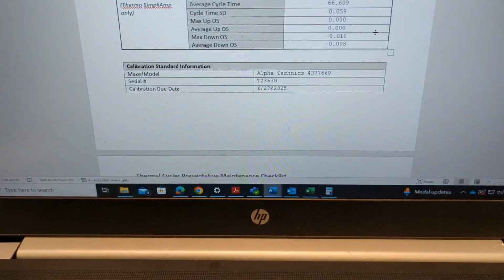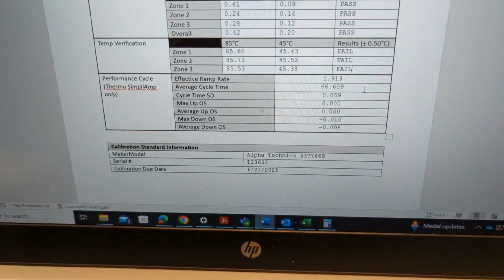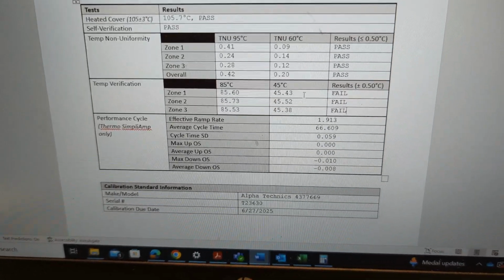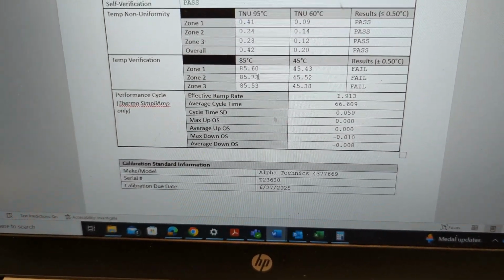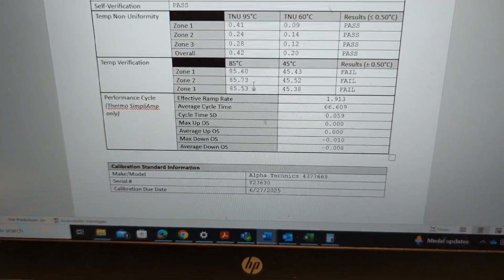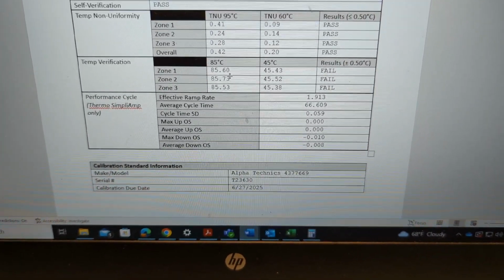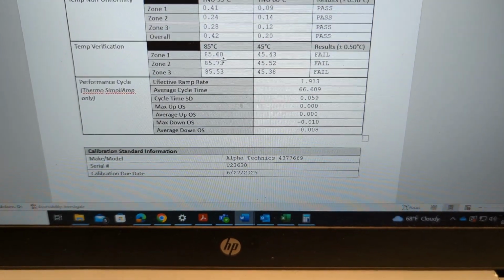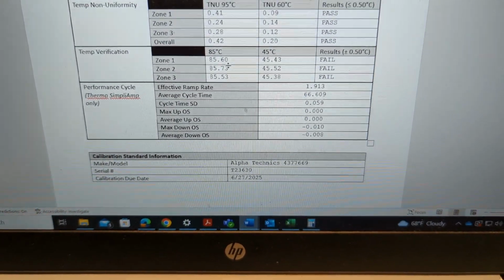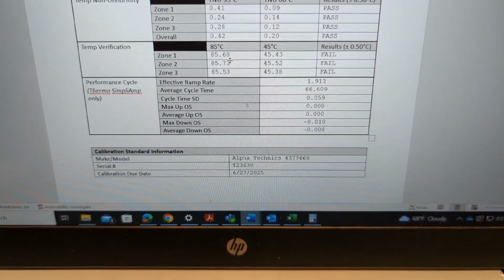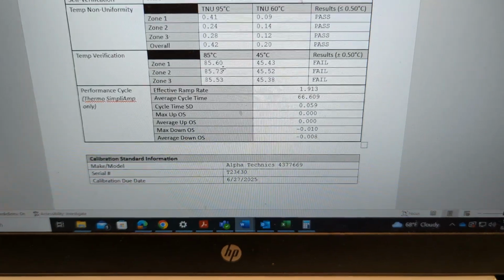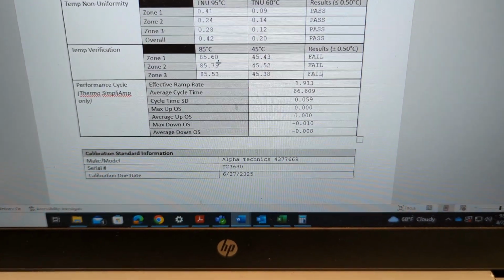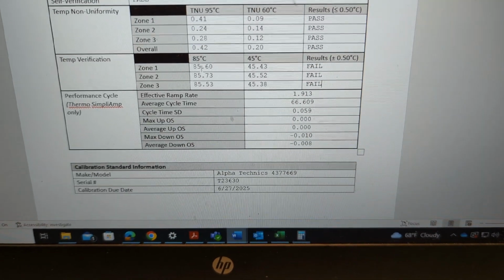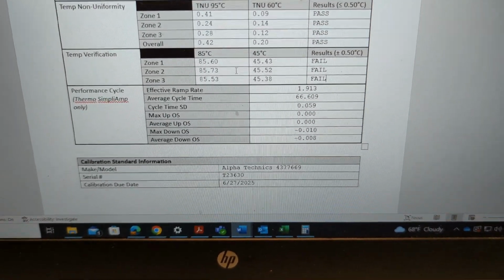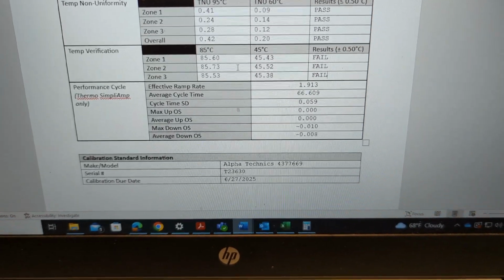Anyway, so this is a portion of a PM report that I do, and you can see here we've got some fails. So this is temperature verification. This is just checking the accuracy of the set temperature, and you can see here the spec is plus or minus 0.5. Actually, for this particular instrument, it's tighter. It's really plus or minus 0.25, but we've developed these in-house standards based on our application needs. Plus or minus 0.5 is fine, and temperature uniformity is actually more important to us. But anyway, these are falling out of spec even for this wider accuracy spec, as you can see.